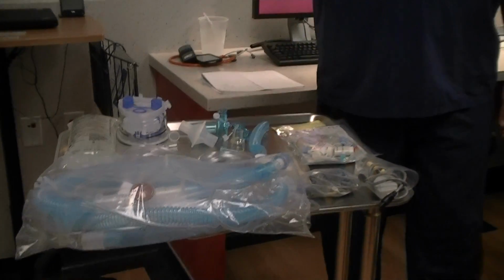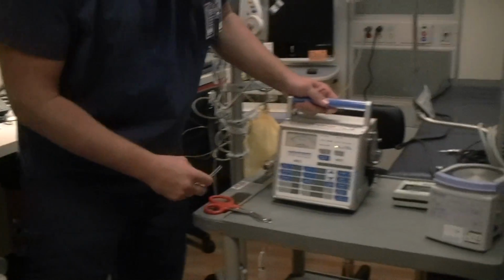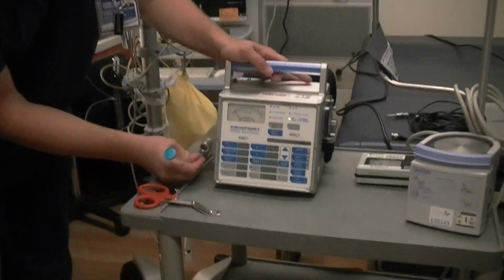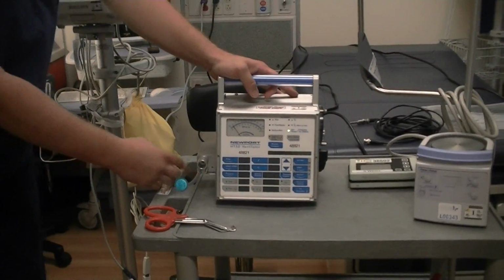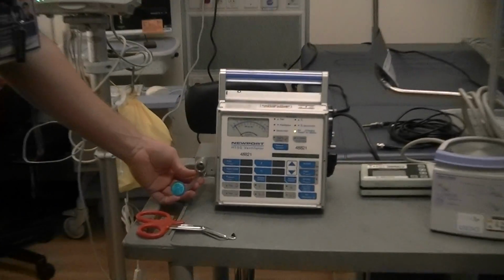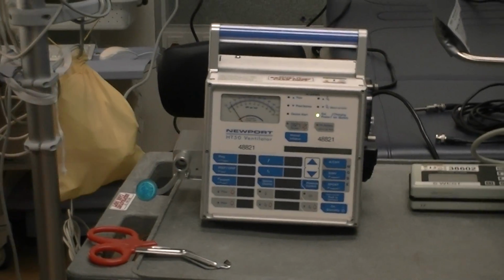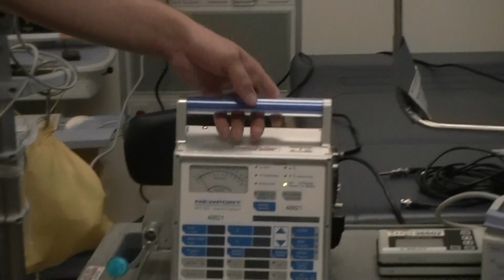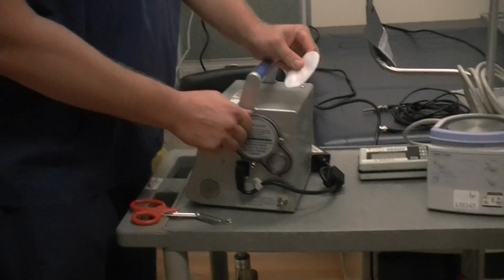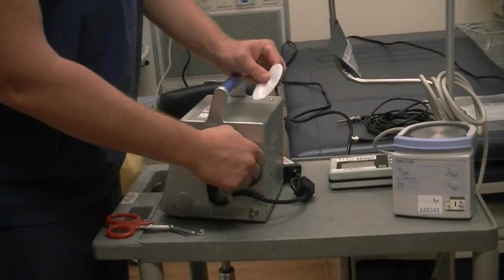The first thing you want to do, make sure your blue line adapter is attached to the proxy line. It's the furthest one to your left, if you're looking at the ventilator. Okay. The next one is you always want to change the filter. This gets changed with every single ventilator setup and circuit change.